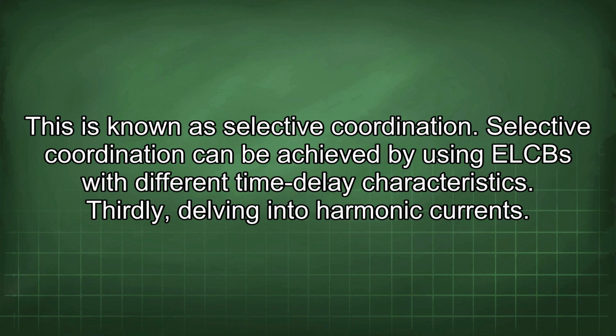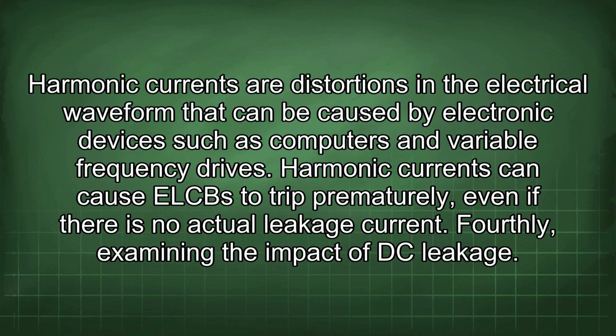Thirdly, delving into harmonic currents. Harmonic currents are distortions in the electrical waveform that can be caused by electronic devices such as computers and variable frequency drives. Harmonic currents can cause ELCBs to trip prematurely, even if there is no actual leakage current.